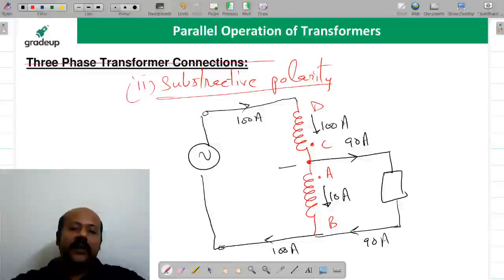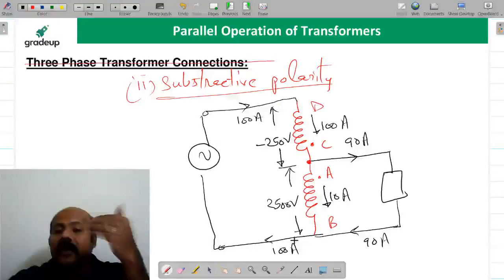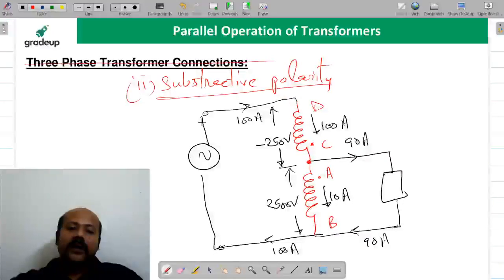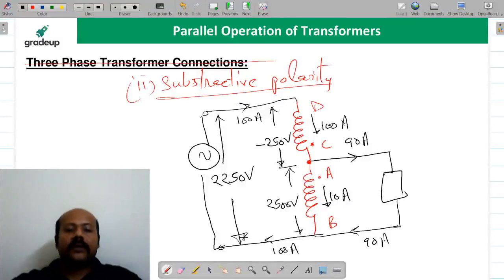Suppose the source is connected here. Now if this is 100 ampere, this is going to be 100 amperes, and 10 ampere here, 90 ampere here, so it is going to be 100 amperes here. Now this voltage, we are saying AB section as 2500 volts, and this voltage with the reverse polarity is going to be minus 250 volts. That is the meaning of subtractive polarity. So what is the total voltage here? You get 2500 minus 250, so it is going to be 2250 volts.